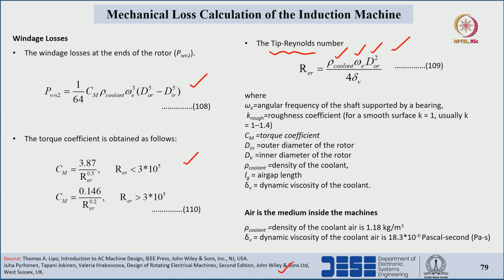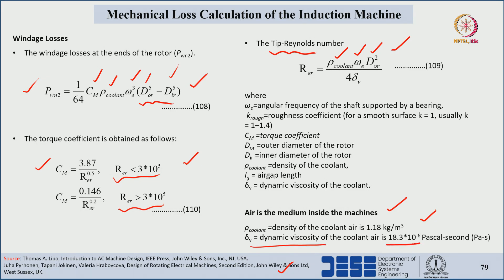After selecting the tip Reynolds number range, we calculate the torque coefficient, then substitute the torque coefficient, coolant density, angular frequency of the shaft, and the outer and inner diameter values of the rotor to calculate the windage losses at the ends of the rotor. Inside machines, air is the medium: coolant density is 1.18 kg/m³ and dynamic viscosity of air is 18.3 × 10⁻⁶ Pascal-seconds.